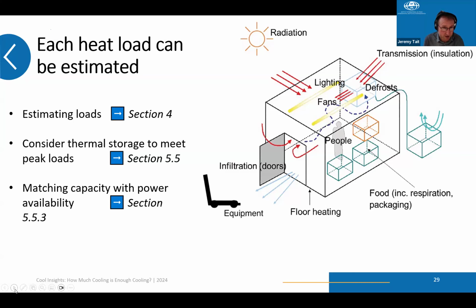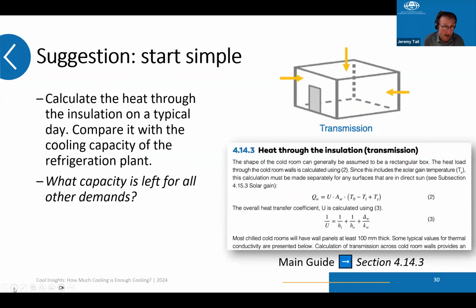But it's a good idea to start simple. On the next slide, you can perhaps start by simply looking at what the heat load is through transmission - there's an equation to help with that. If you know the area of the insulation around the cold room, the thickness and the type of insulation, the formulas given help you calculate the actual heat load that comes through. If you make that relatively simple calculation, you can then look at what capacity in your plant is left over for dealing with everything else, and start to get a feel for just how feasible it is.